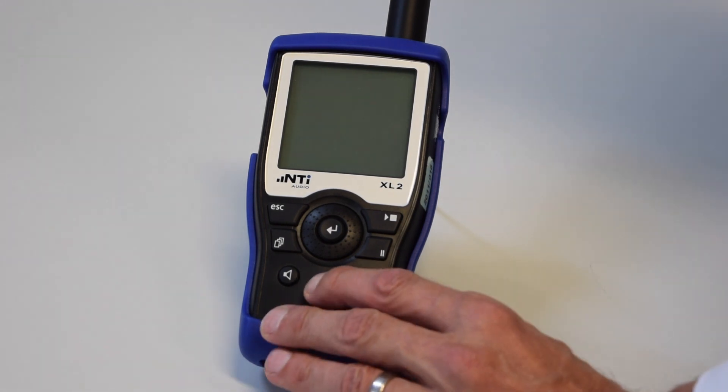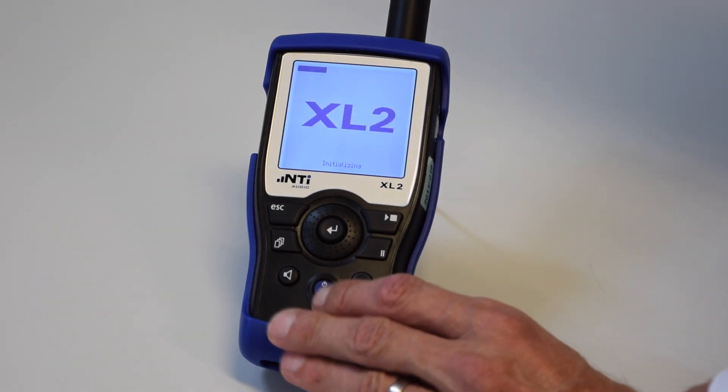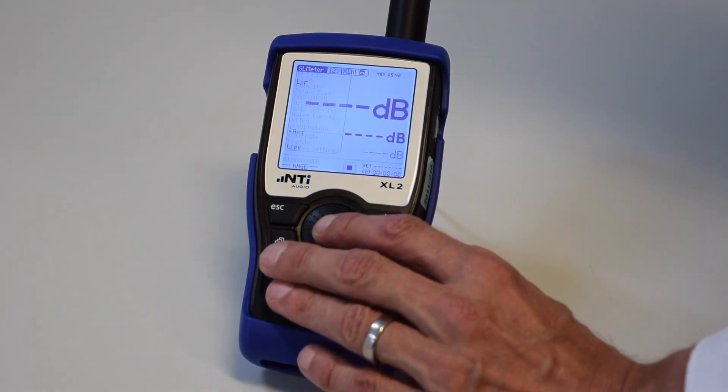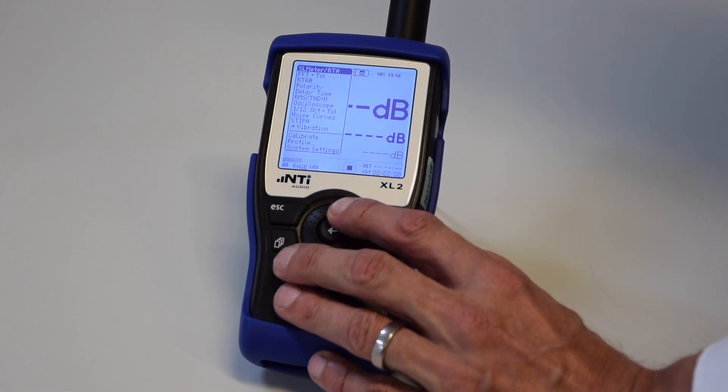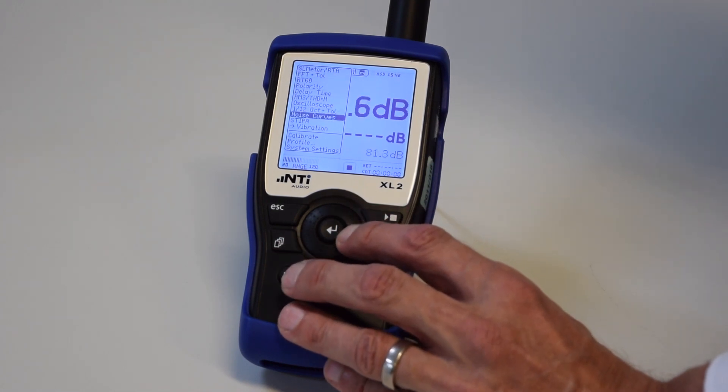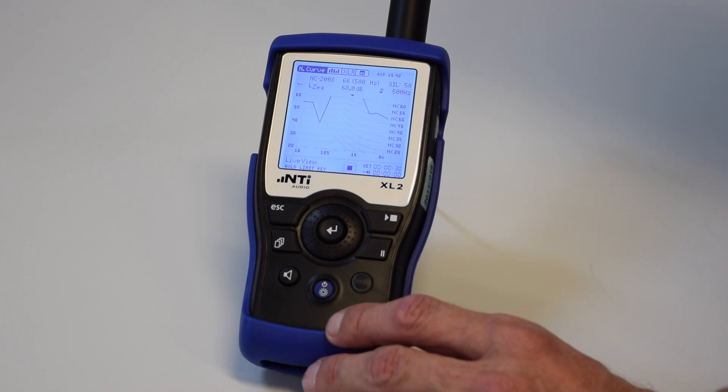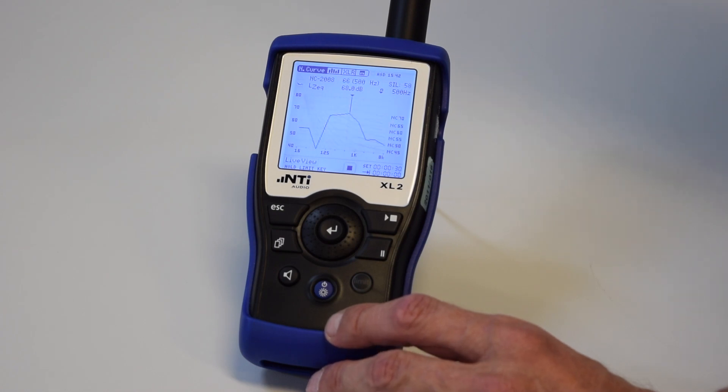We power on the XL2 Analyzer and select the noise curve function in the main menu. This functionality is optional and requires an installed spectral limits option on the instrument.